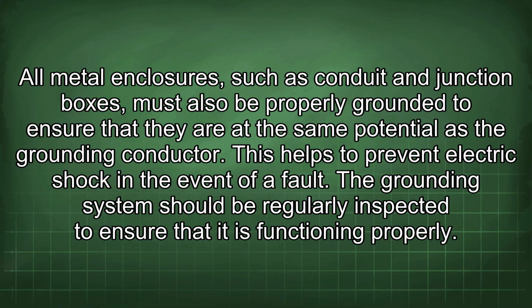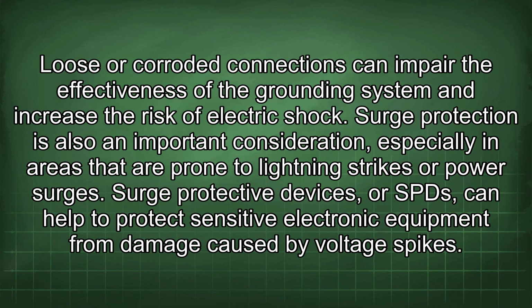The grounding system should be regularly inspected to ensure that it is functioning properly. Loose or corroded connections can impair the effectiveness of the grounding system and increase the risk of electric shock. Surge protection is also an important consideration, especially in areas that are prone to lightning strikes or power surges. Surge protective devices, or SPDs, can help to protect sensitive electronic equipment from damage caused by voltage spikes.